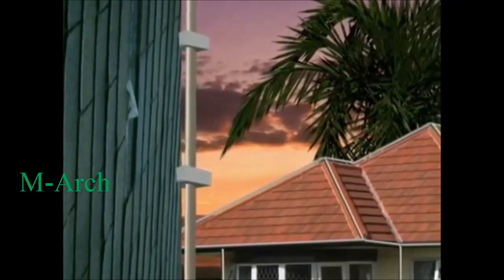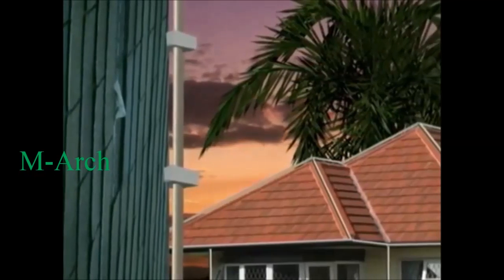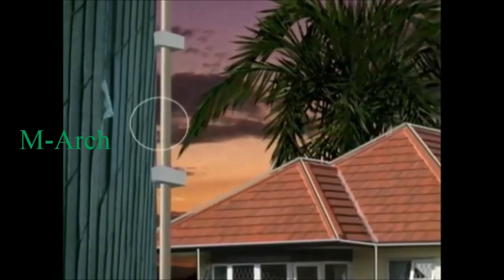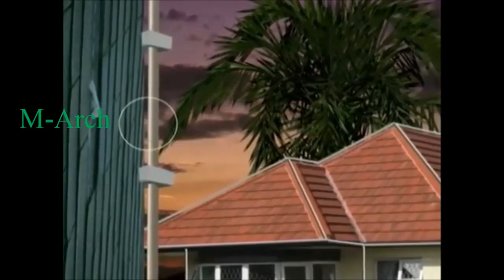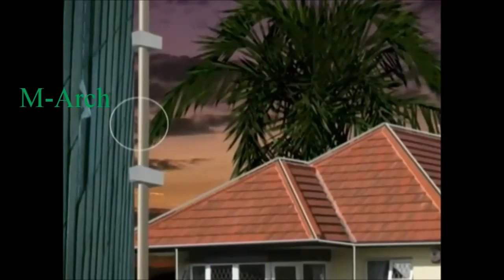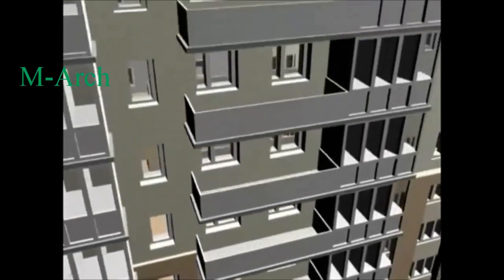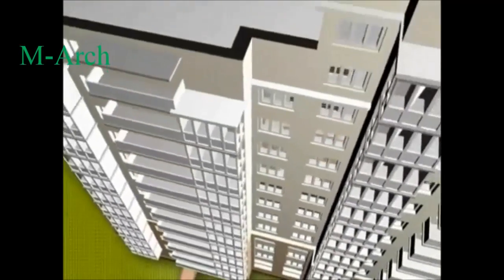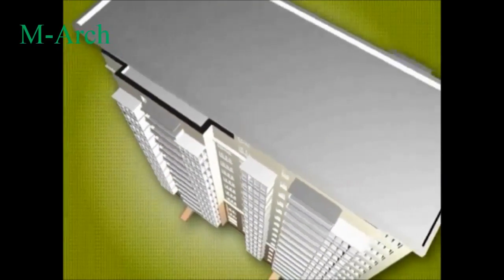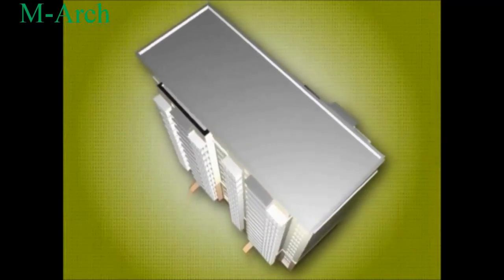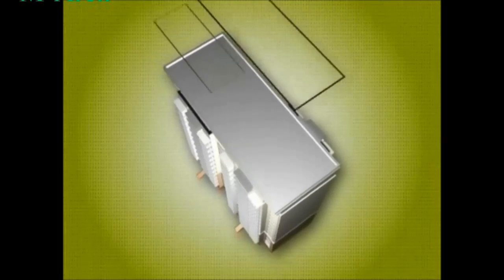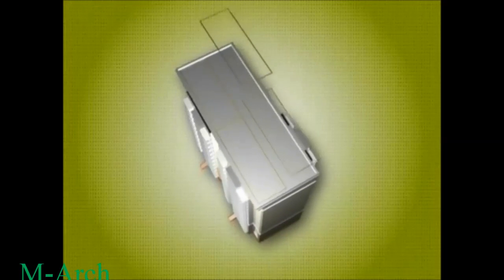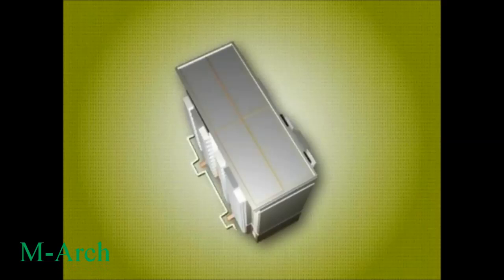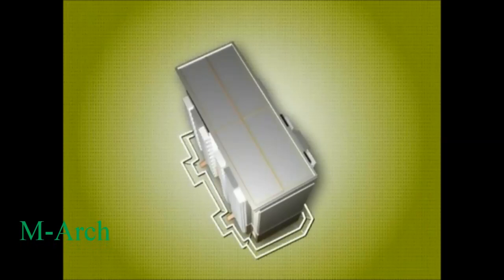Any material with electrical conductivity can be used as down conductors. When the down conductors pass through external walls made of flammable material, a specific distance needs to be maintained between the wall and the conductors. When the arrestor system is installed in high-rise buildings, it is to be ensured that down conductors are installed every 10 to 20 meters. When down conductors are placed parallel to the roof, they are to be linked using ring conductors to prevent fire outbreaks.